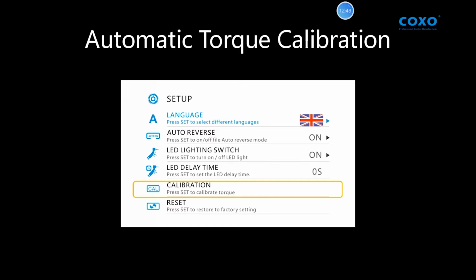Another case is when you change the control angle—the same thing applies. You need to do calibration again, because the speed and torque the machine shows might say 1.5 Newton, but in fact the handle outputs 2 Newton, and that will break the file. So remember to do calibration when you change the control angle.